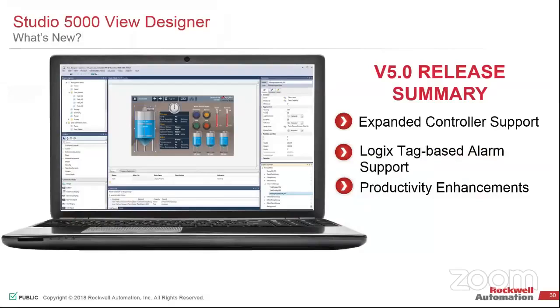So if you guys are looking for a new PanelView application going forward, default should still be the PanelView Plus 7. That's, to tell you the truth, what I'm comfortable with in process and in our industry. But looking forward, especially if you're on an LA style design on a newer software and you don't have a requirement for the process objects, that's a big limitation that we have with this product. If you're using the PlantPAx process objects or anything similar to it, they do not exist in this newer platform.